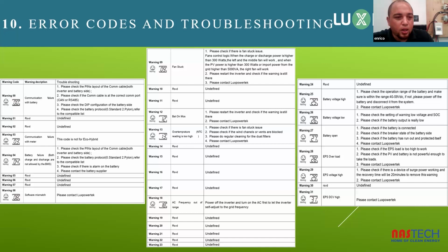In this case, when checking the battery communication failure, it can usually mean that the battery's comms cable is not correct. Yeah, I got a cable tester. For the batteries, I'm still getting to the compatibility list. I have a cable here. So when creating the cables as well, please make sure that you use the cable tester to make sure that the connections are correct and that you have the right cable.